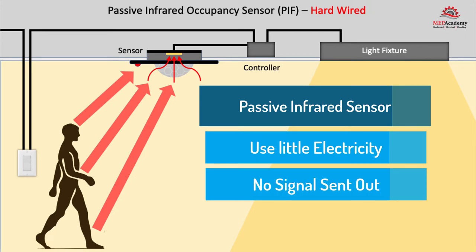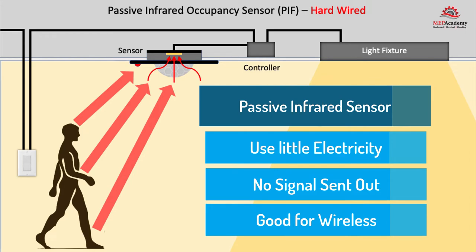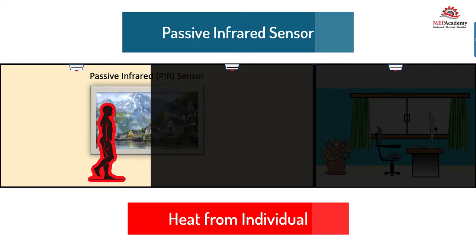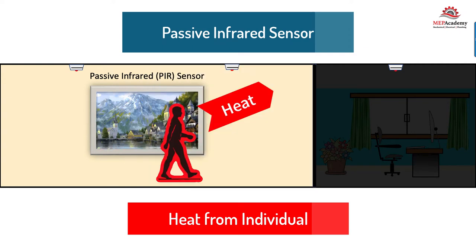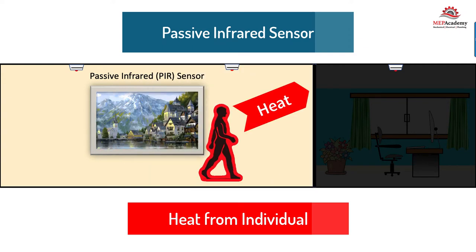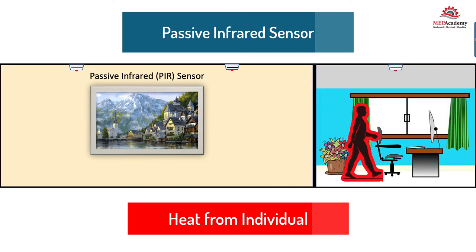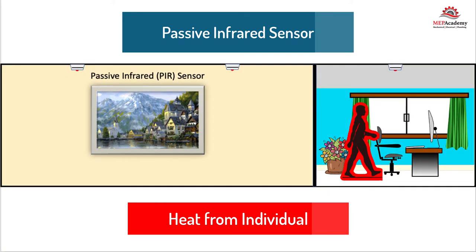A passive infrared sensor uses very little electrical power because it doesn't constantly send out a signal like an ultrasonic sensor, making it great for wireless communication. The passive sensor picks up the heat emitted from individuals in the space, so it needs a direct line of sight to work. It doesn't work well when there are obstructions like partitions or bookshelves.